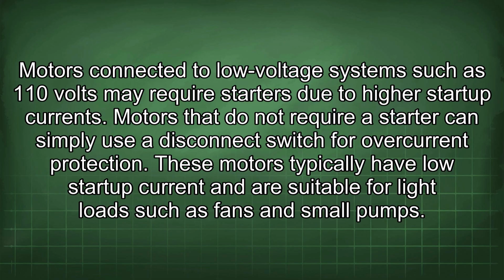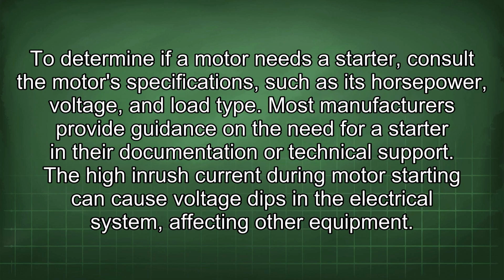Motors that do not require a starter can simply use a disconnect switch for overcurrent protection. These motors typically have low startup current and are suitable for light loads such as fans and small pumps. To determine if a motor needs a starter, consult the motor specifications such as its horsepower, voltage, and load type. Most manufacturers provide guidance on the need for a starter in their documentation or technical support.